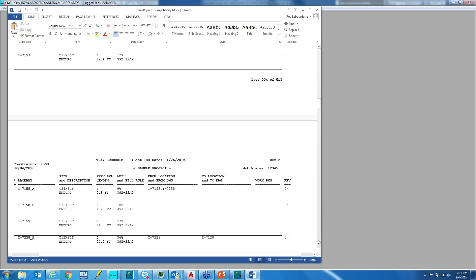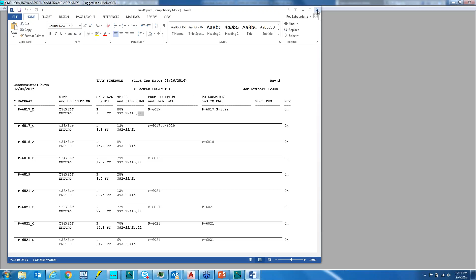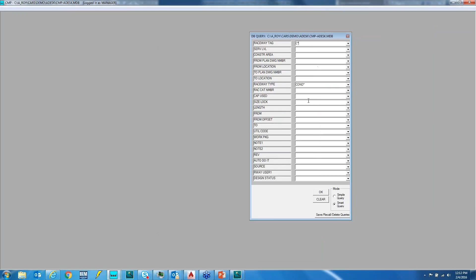This tray, according to the program, is full. As a matter of fact, this is a low voltage tray, and there are two sections of the code that apply to this tray, because I have some cables that are smaller than 4-aught and some that are larger than 4-aught, and there are two different fill requirements in the code to calculate that fill correctly, and the program is capable of handling that.